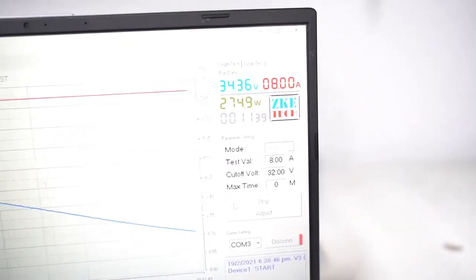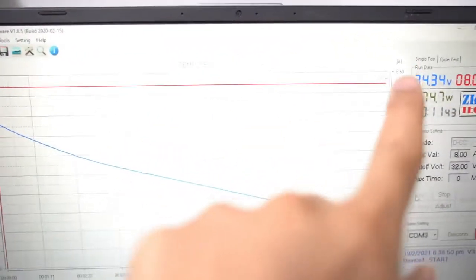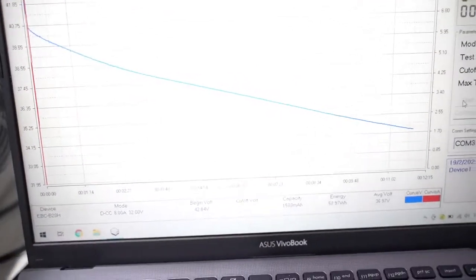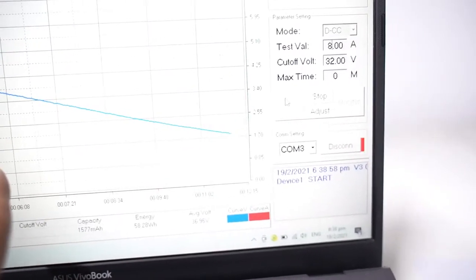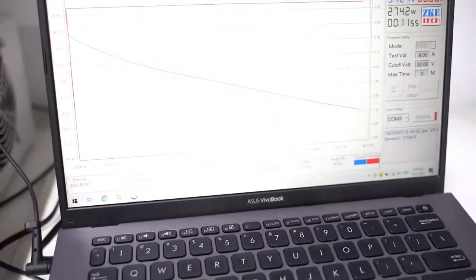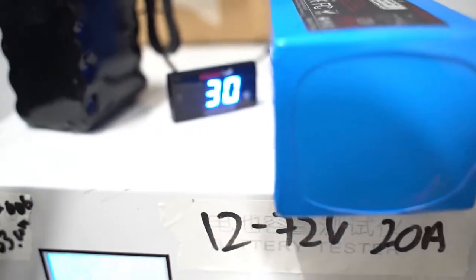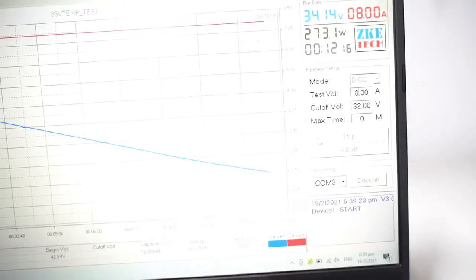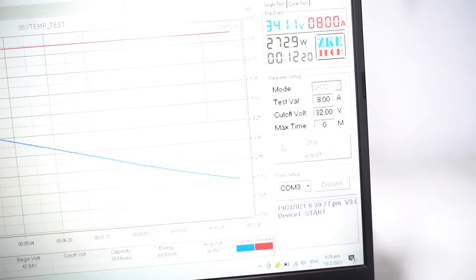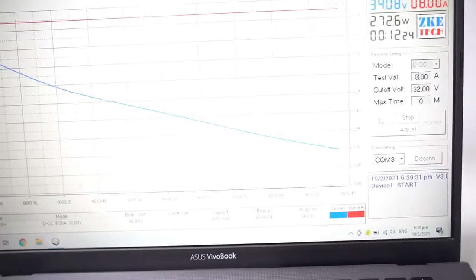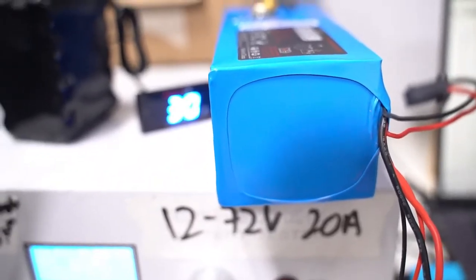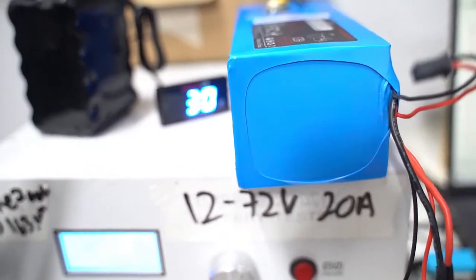Alright, it's been about 11 minutes as the timer says. We are still drawing 8 amps consistently, as you can see from that red curve. The blue discharge curve is at about 34.15 volts, and it's still stable. The temperature has risen to 30 degrees Celsius, which is normal because it generates heat when it discharges. It's at 12 minutes now, as the timer says, so we're still waiting for it. It has already exceeded the capacity when the battery was running at sub 10 Celsius. So it's looking like it's going to perform better right now, but let's check back in a bit.